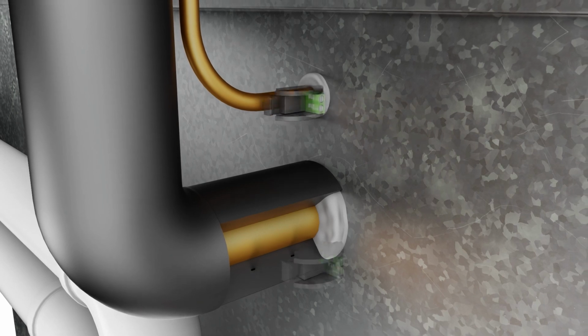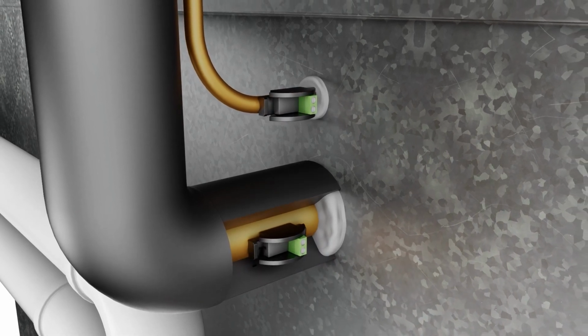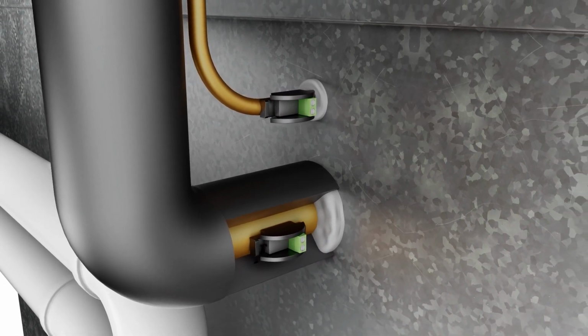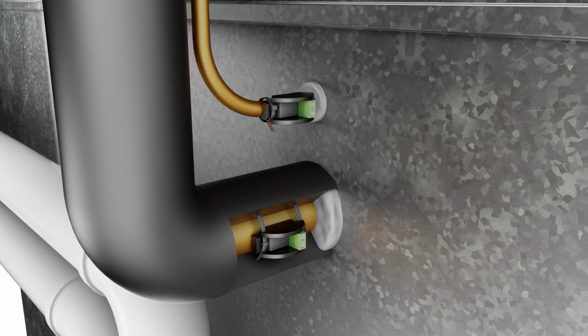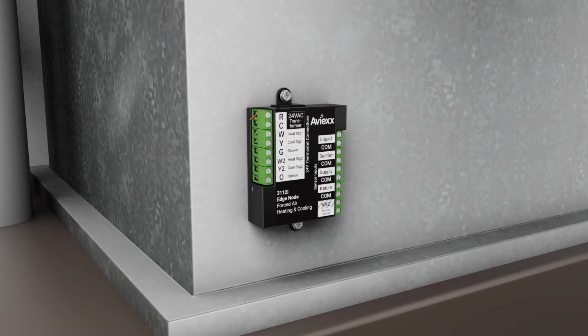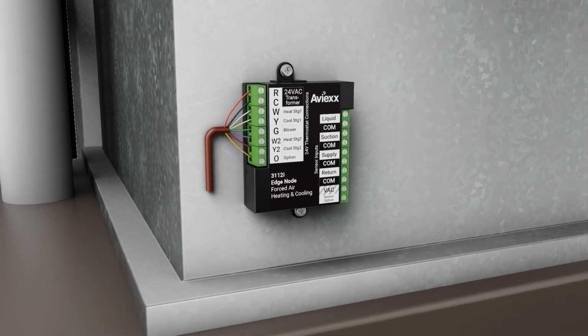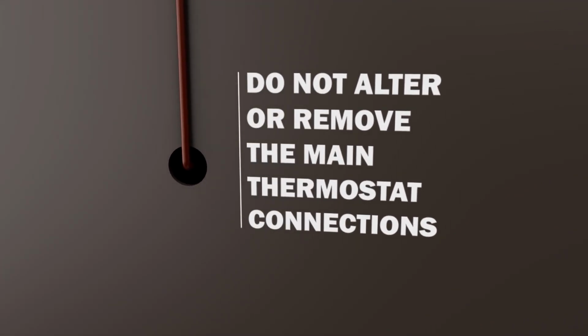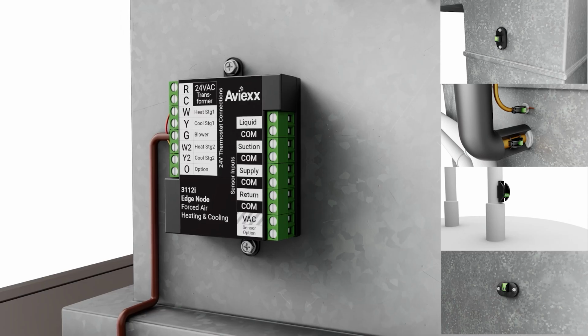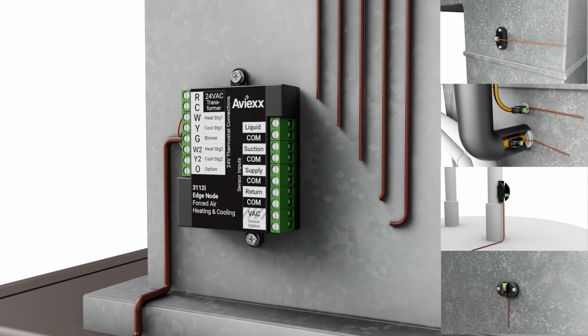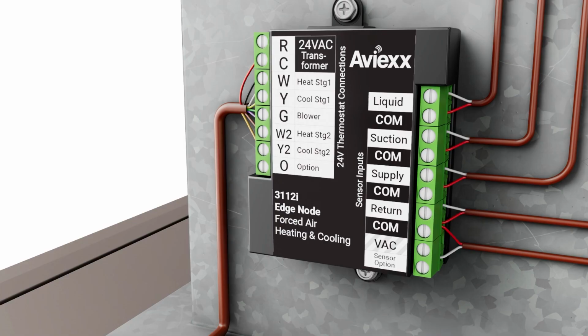Mount the refrigerant sensors as closely as possible to the cooling coil on the exterior of the equipment using the cable ties provided. Connect the thermostat terminals on the Edge node to the thermostat terminal on the equipment main control. Do not alter or remove the main thermostat connections. Connect the sensors to the Edge nodes following the markings on the label.